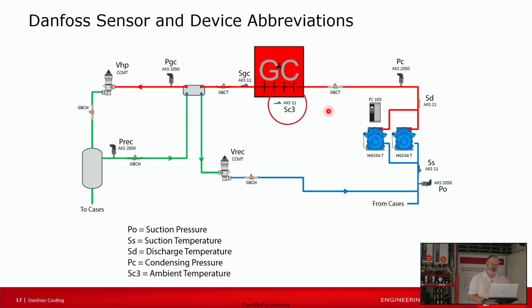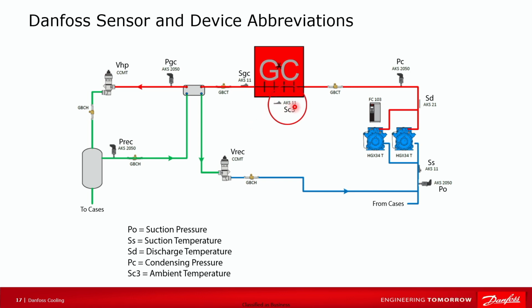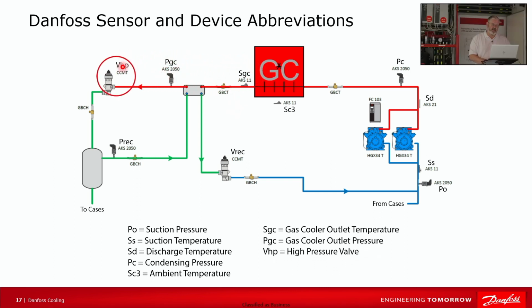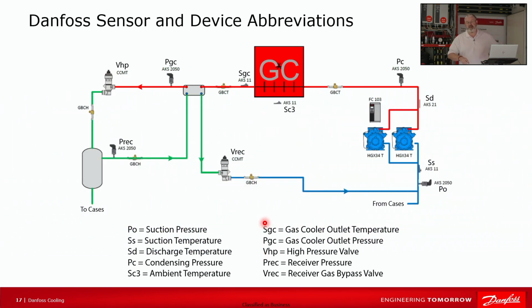S3C, I don't have a good answer for. It's an anomaly. S means temperature sensor. C, I'm guessing, means condenser. The 3 is a mystery to everyone. And we're not changing it. Then we have a temperature sensor on the gas cooler outlet. A pressure transducer on the gas cooler outlet. Now we have a new one, the V for valve high pressure. A pressure for the receiver. And then the valve for the receiver. So the uppercase letter, and this is all through our software and various controllers: P represents a pressure transducer, then the descriptor. S represents a temperature sensor, then the descriptor, and then the same for the V for valve. Now that face that just went across is because I just discovered that PowerPoint has motion paths. I'm childish and I could not help myself.